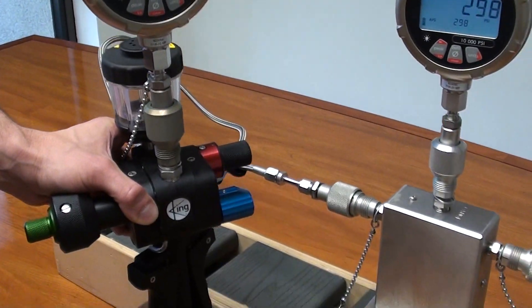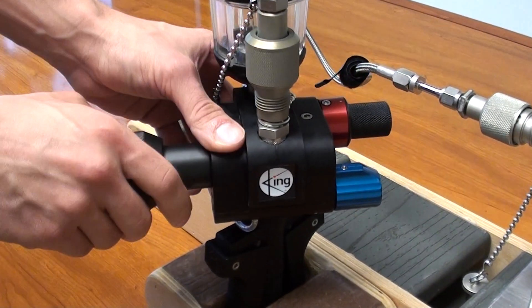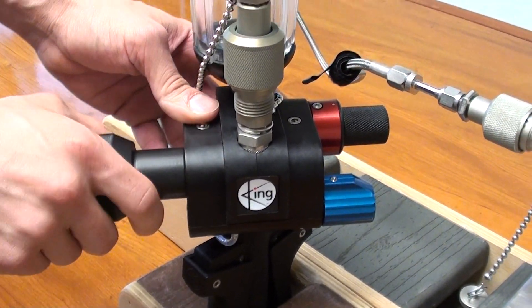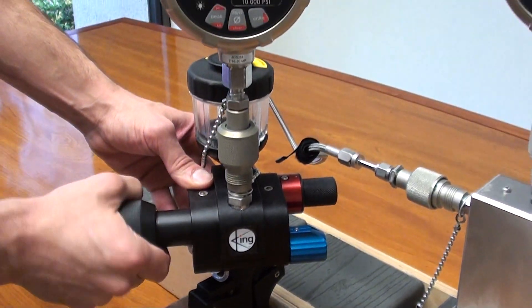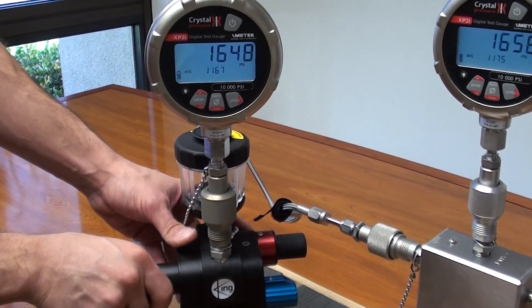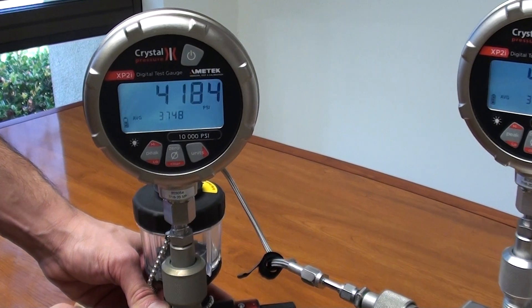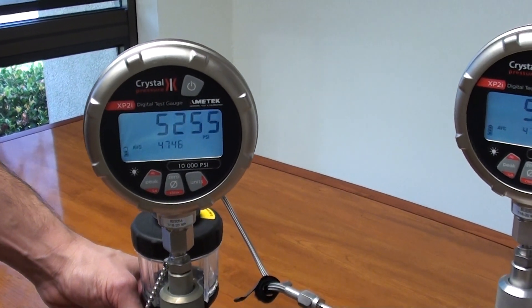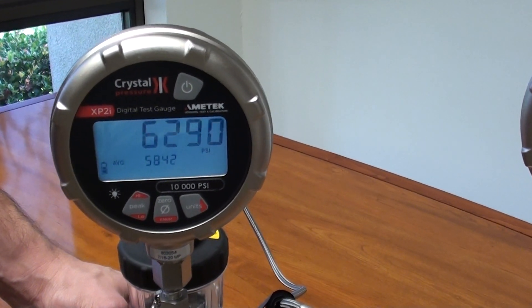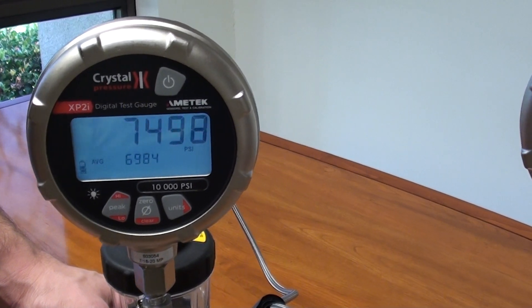After that we're going to use the volume adjuster knob to generate high pressure on our hand pump. So as you can see by rotating the knob we're increasing the pressure and we're going to take this all the way to between 9500 and 9800 PSI.